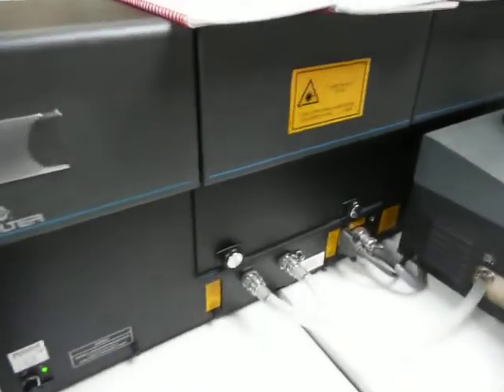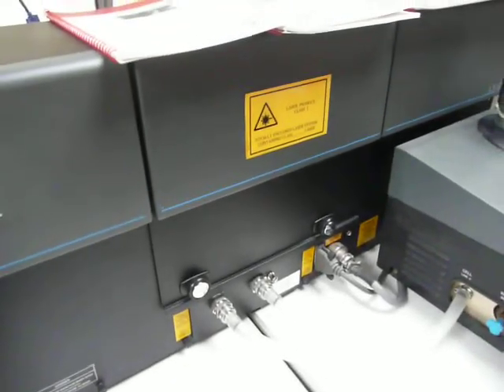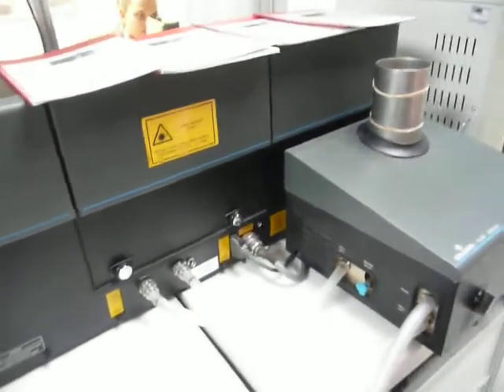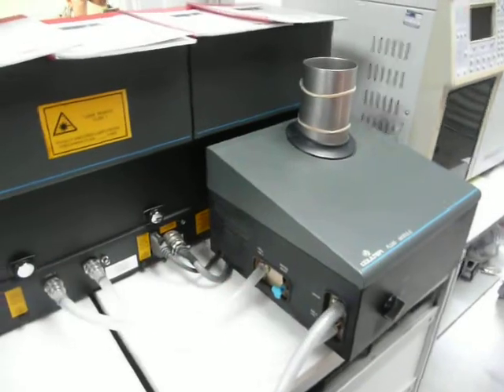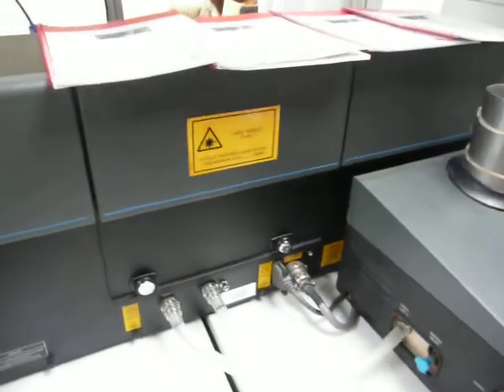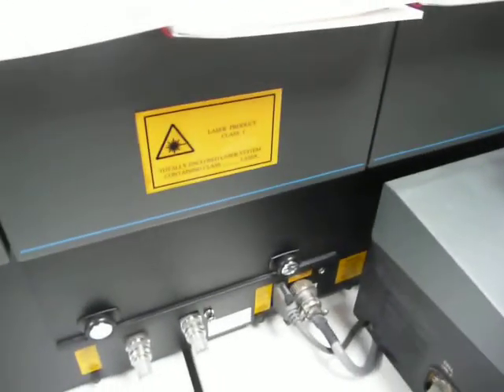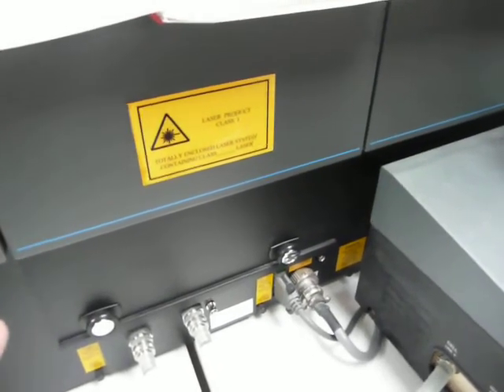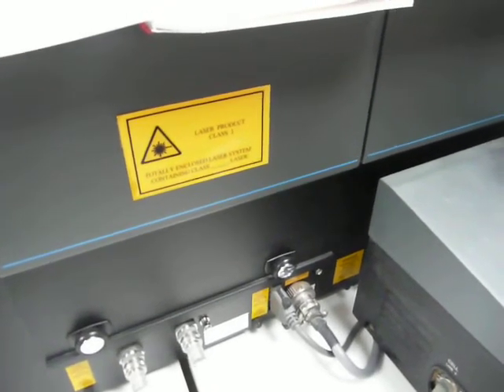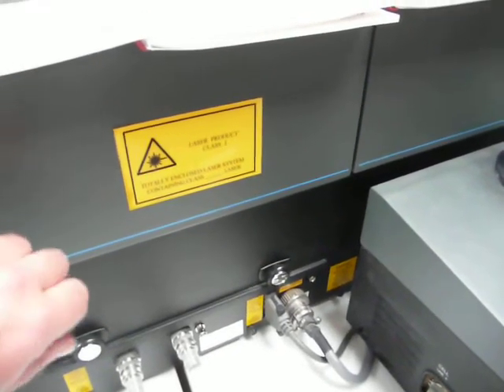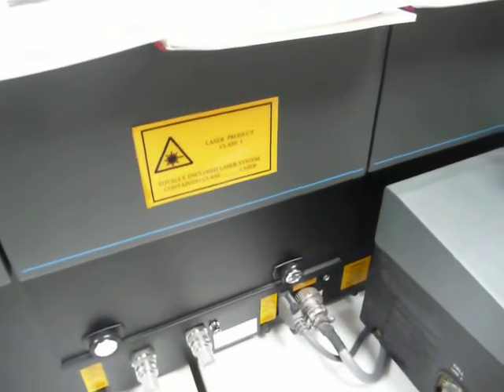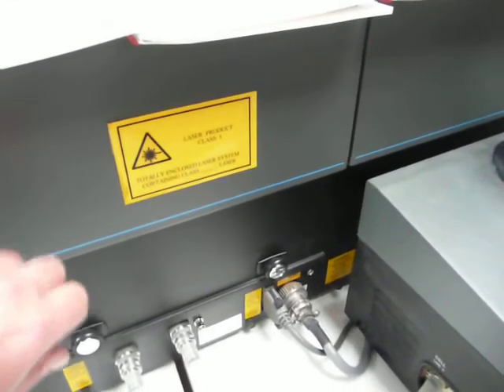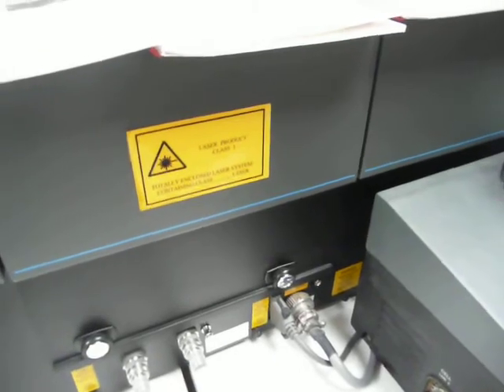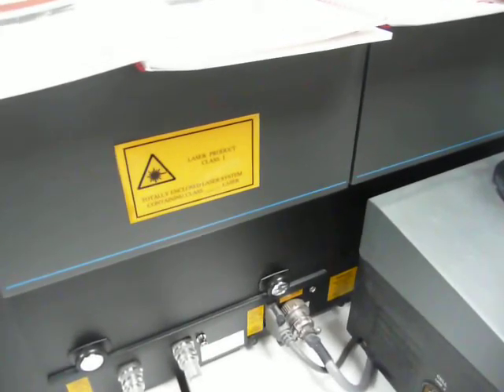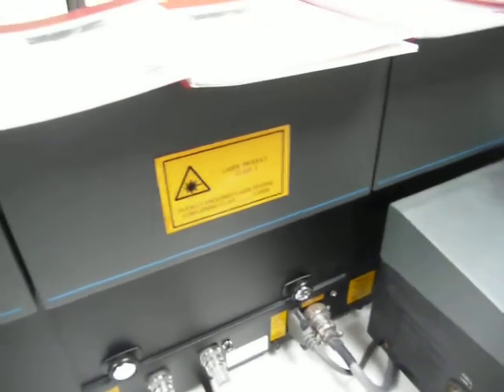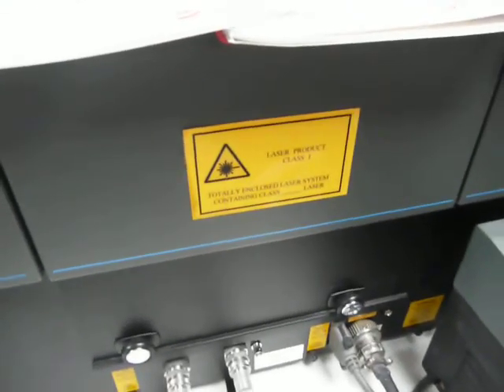This is the Coulter LS230, and this is the fluid module here, and this is the front of it. It's important beforehand, and I'll show this later, that when it's transported, the locking screws on the locking plate will be in the home position. Before the instrument is used, it's important to back them off with a small Allen key. Again, we'll show you that later on in the video.